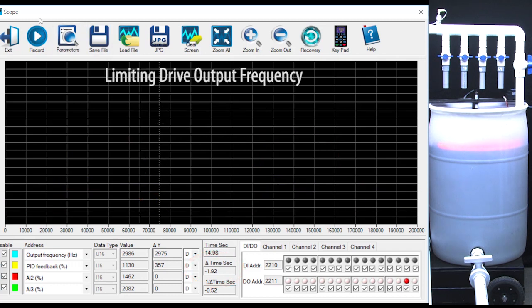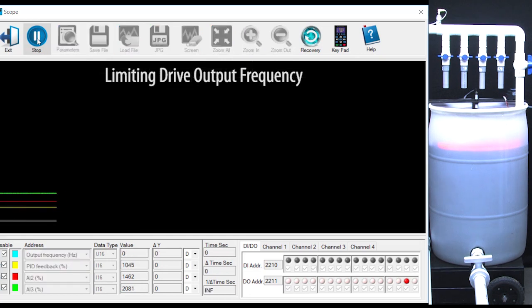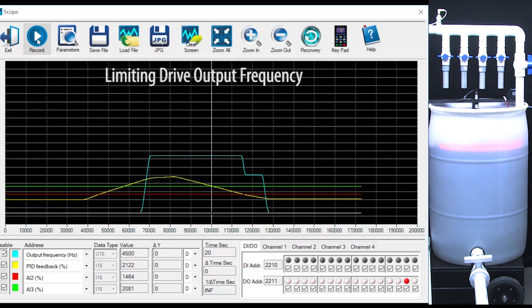And just like in the previous video, you can change the max PID frequency output. I set it to 75%, ran the drive and got this. Sure enough, the max output frequency is limited to 45 Hz, which is 75% of the drives max 60 Hz.